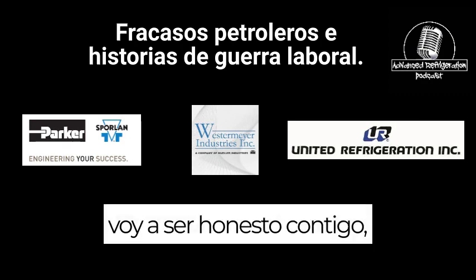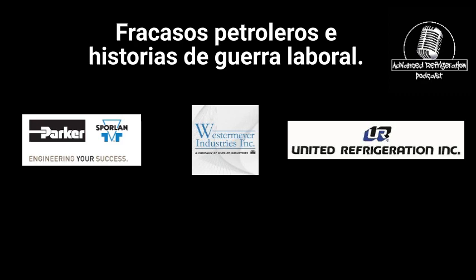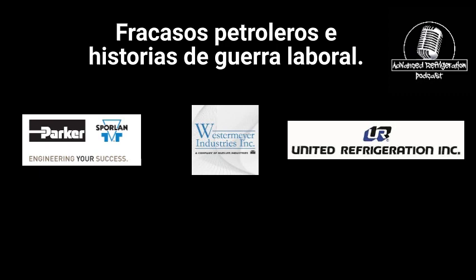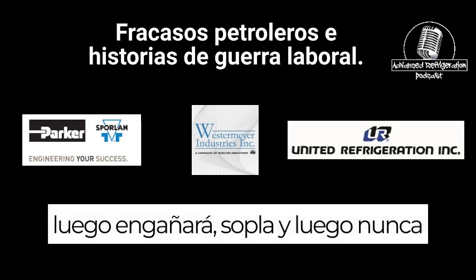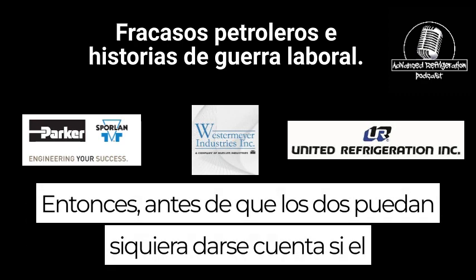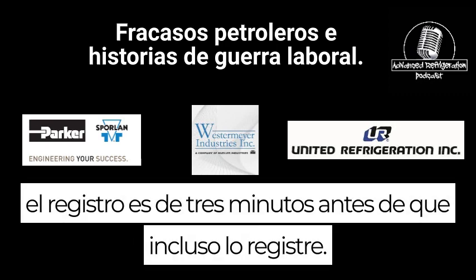I'm going to be honest with you, I've never seen one of those in Warren. So we took over an account in a half-one program, and I started setting them up where the control locks on for like 5 minutes, because it blows and then it'll trip, it blows, and then you never know because it resets right away. So before the E2 can even realize, the logging is 3 minutes before it even logs it.